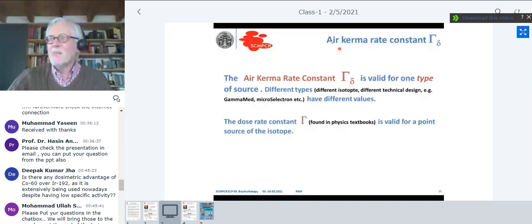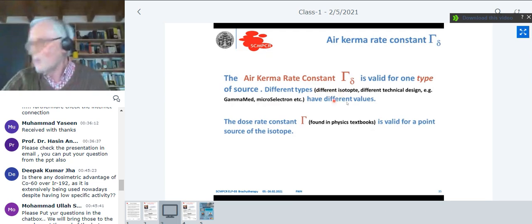Something we need to keep in mind is that such an air kerma rate constant is valid for only one type of source, which means one technical design of source. So the air kerma rate constant for a Varian source is different than the air kerma rate constant for a Nucletron source, or Varian, or Elekta, or whichever you have. Different types, meaning either different isotopes, but even with the same isotopes, different technical designs have different values.